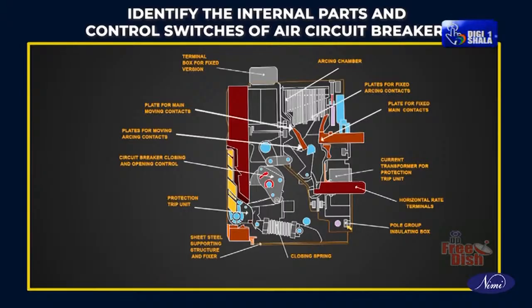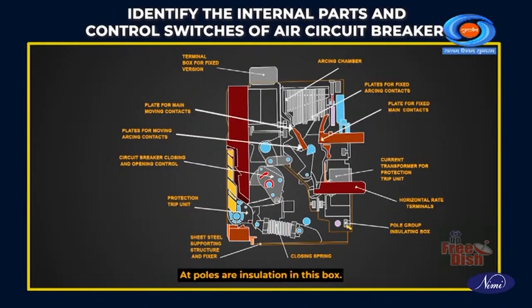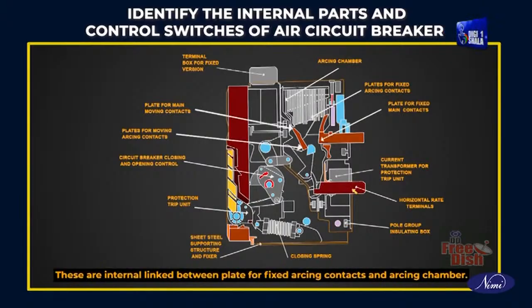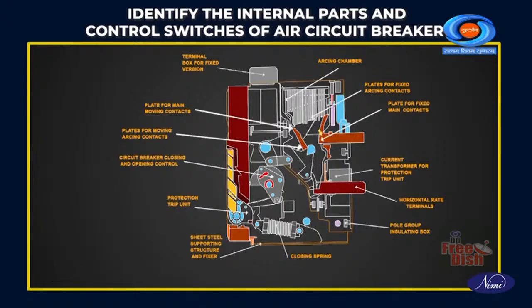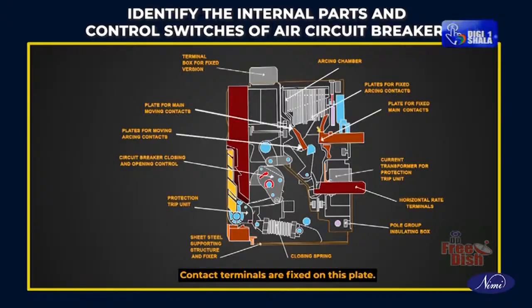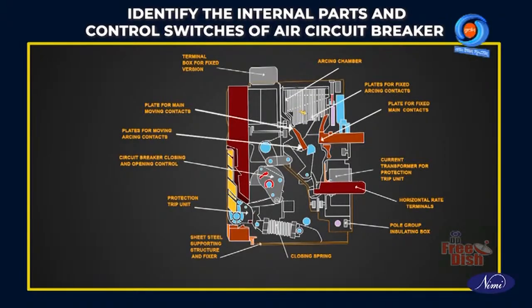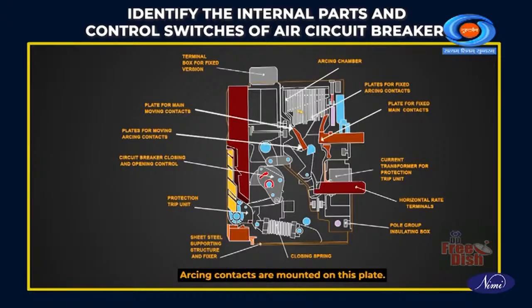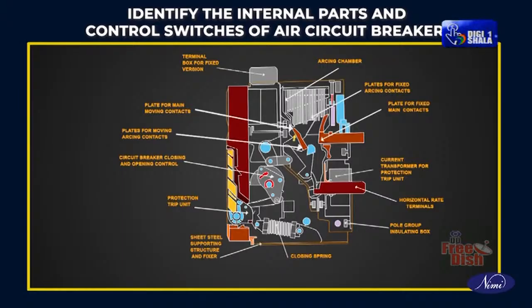Pole group insulating box: the poles are insulated in this box. Horizontal rear terminals: these are internally linked between the plate for fixed arcing contacts and the arcing chamber. Plate for fixed main contacts: contact terminals are fixed on this plate. Plates for fixed arcing contacts: arcing contacts are mounted on this plate. Plate for main moving contacts.